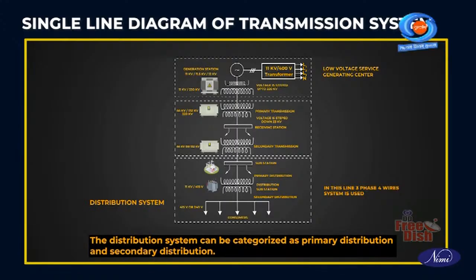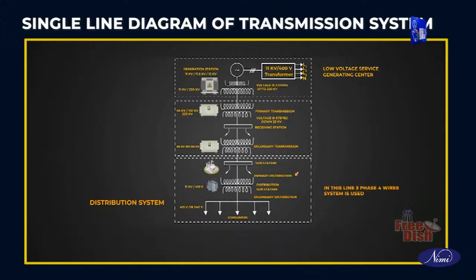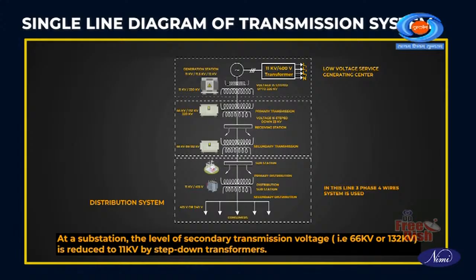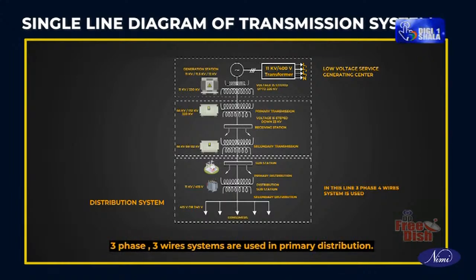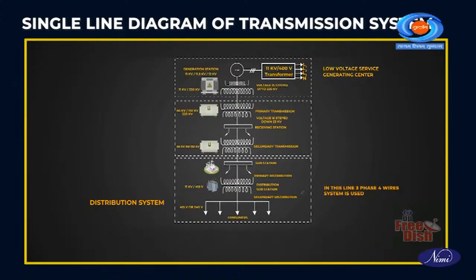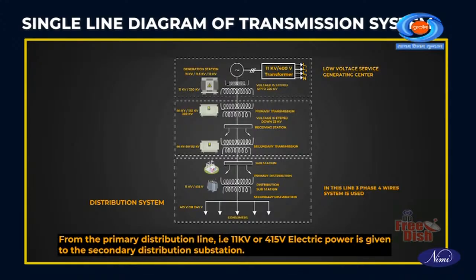Distribution system can be categorized as primary distribution and secondary distribution. Primary distribution. At a substation, the level of secondary transmission voltage, that is 66 kV or 132 kV, is reduced to 11 kV by step-down transformers. 3-phase, 3-wire systems are used in primary distribution. Secondary distribution.